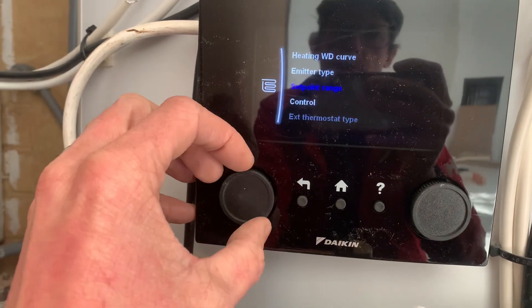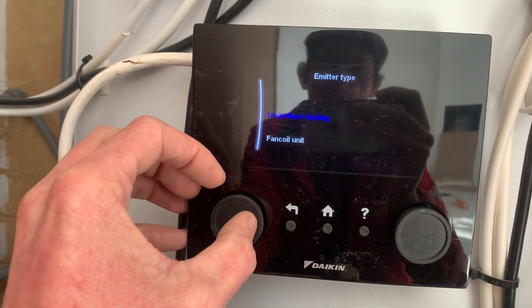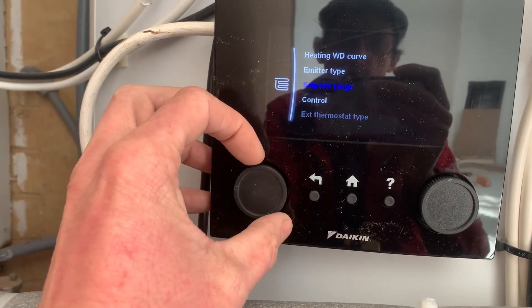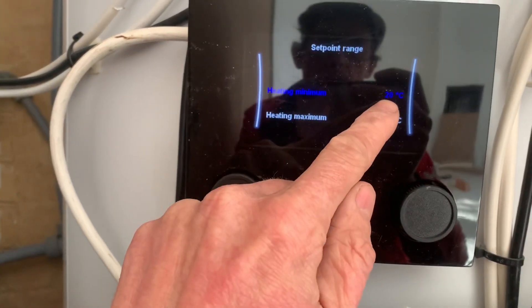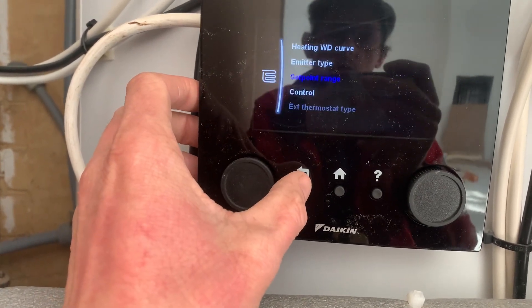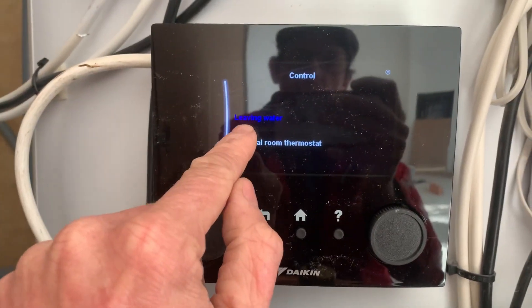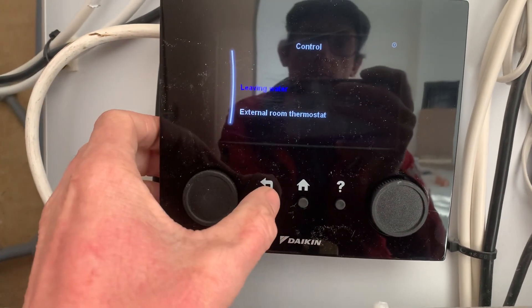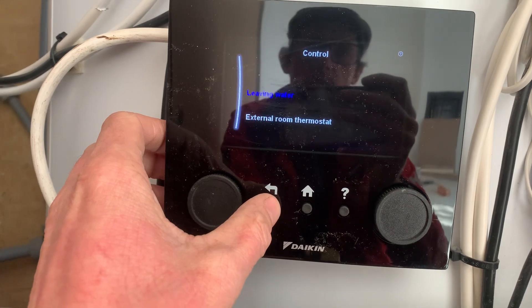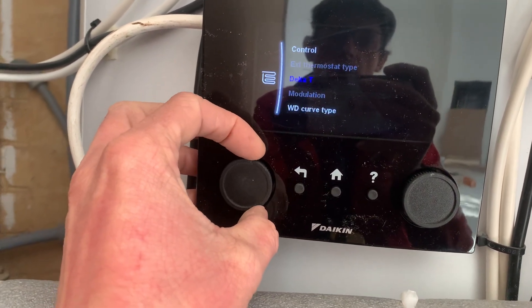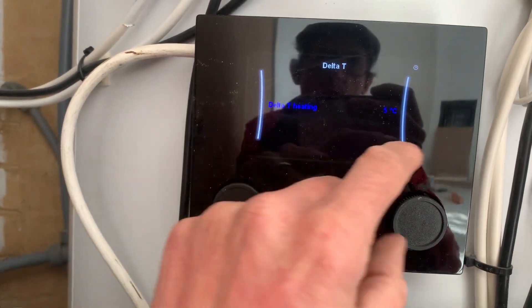For the emitter type — to get the DT5 — we have underfloor heating. Set the set point range lower to 20 on the heating minimum. Control: put that on leaving water, which is dependent on the water temperature. And then the DT we can adjust, but we'll leave it at five.